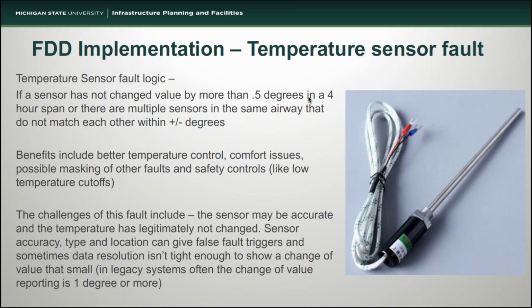Now again, like the airflow sensor, we have a lot of benefits of this because we're going to control the air handler's heating and cooling based on these measured temperatures. So if they're significantly too high or too low, again, you're going to condition more energy than you should. But a lot of these sensors also act as safeties, like a low temperature cutoff to keep from freezing a cooling coil. And if that sensor is not reporting correctly, then you could potentially damage your equipment.